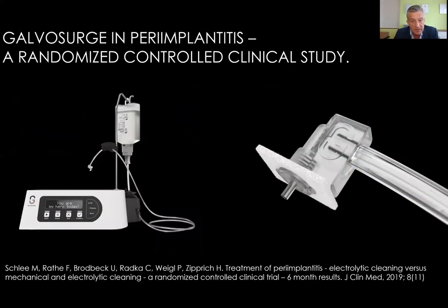This is the device we developed finally. It's a machine with a touch screen which allows something to change, which starts the pump, because we need the solution to be sprayed on the implant. And on the right side, you see the spray head. This little metal notch has to be in contact to the implant, and this will load the implant. And you see a little sponge. This holds the electrolyte in place.